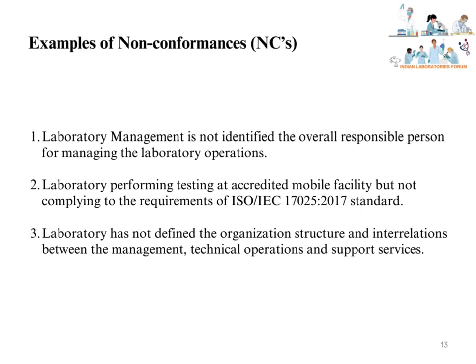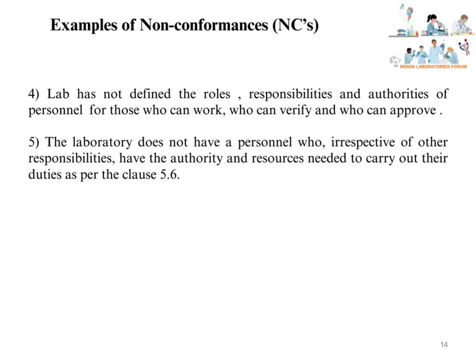Examples of non-conformances as per Clause 5.0: Laboratory management is not identified as the overall responsible person for managing laboratory operations. A laboratory performing testing at an accredited mobile facility but not complying with the requirements of ISO IEC 17025:2017 standard. The laboratory has not defined the organization structure and interrelationships between management, technical operations, and support services. The laboratory has not defined the roles, responsibilities, and authorities of personnel for who can work, who can verify, and who can approve. The laboratory does not have personnel who, irrespective of other responsibilities, have the authority and resources needed to carry out their duties as per Clause 5.6.